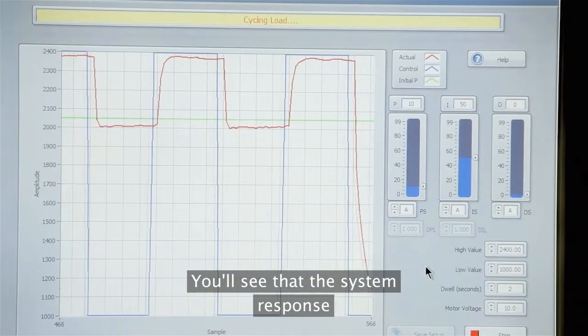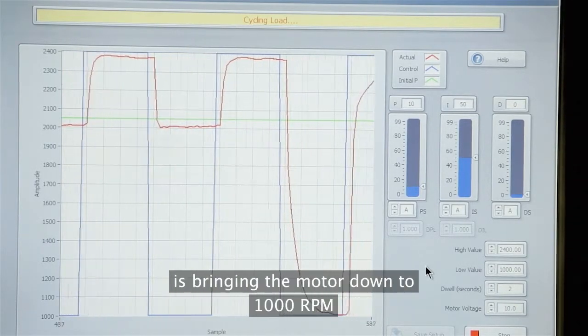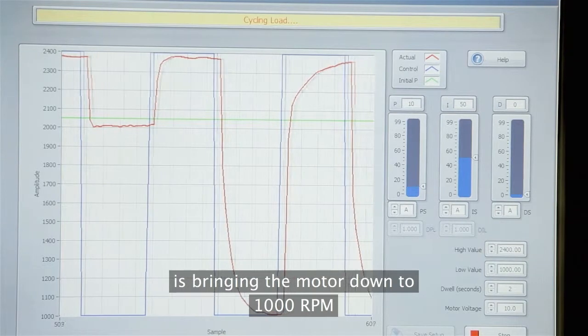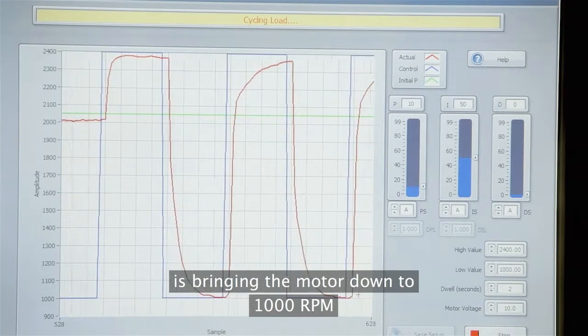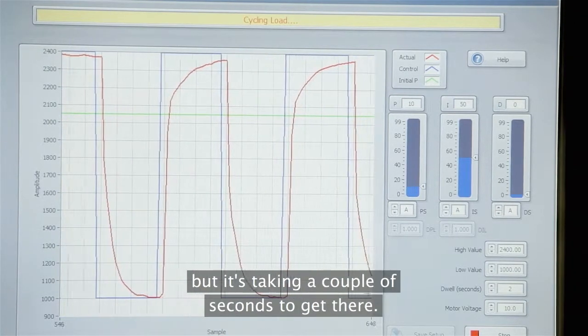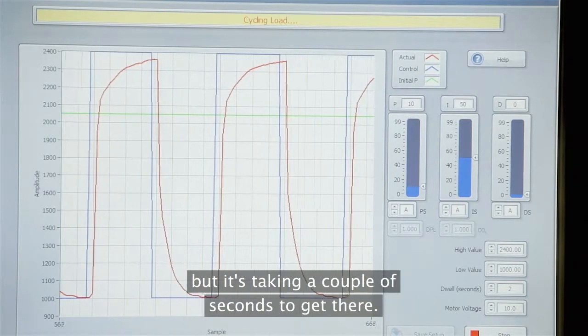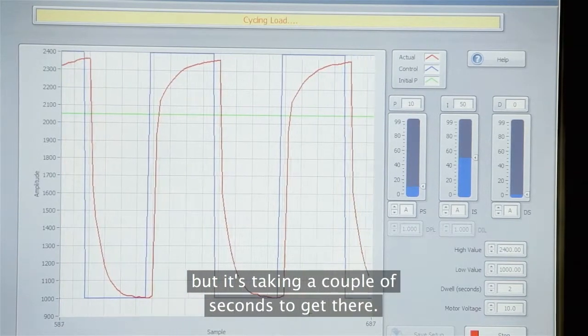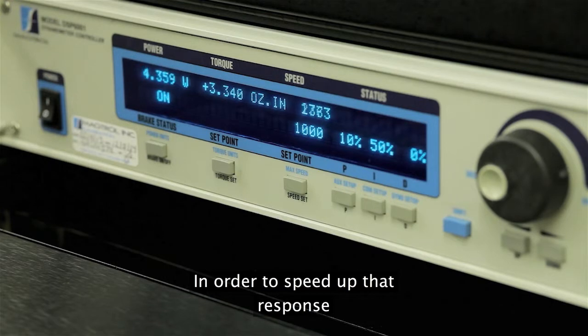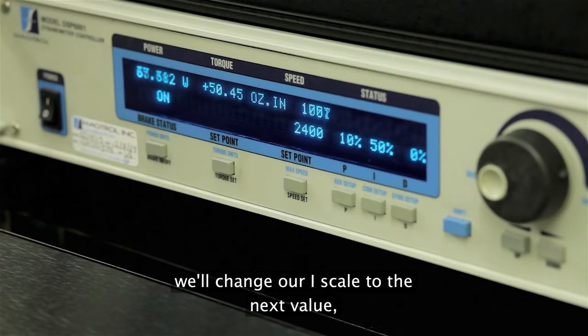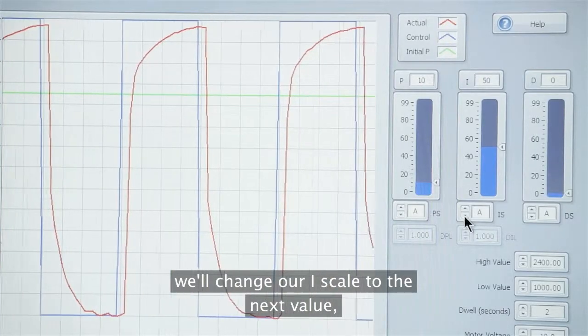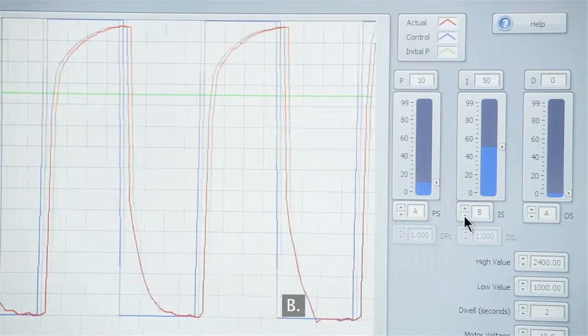And you'll see that the system response is bringing the motor down to 1000 RPM, but it's taking a couple of seconds to get there. So in order to speed up that response, we'll change our I scale to the next value, B.